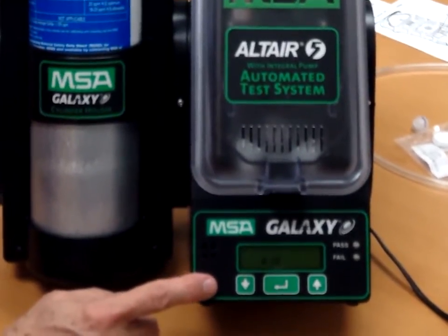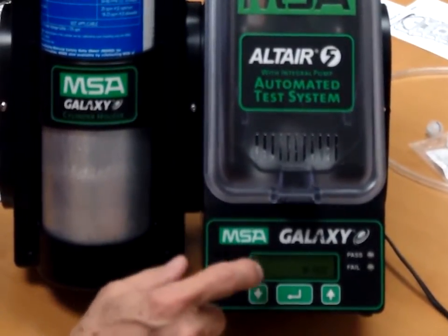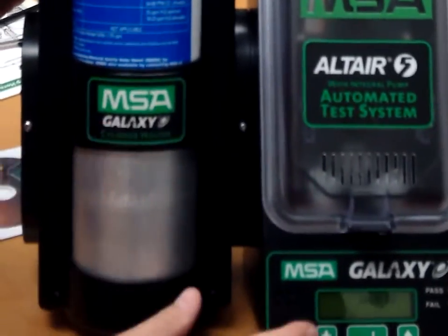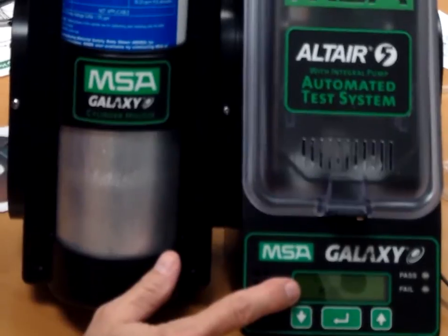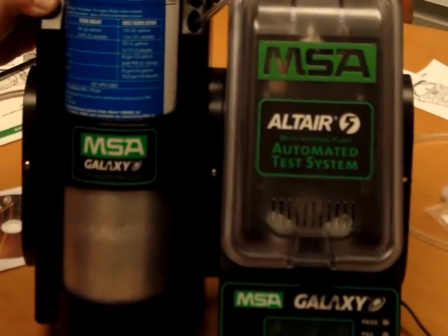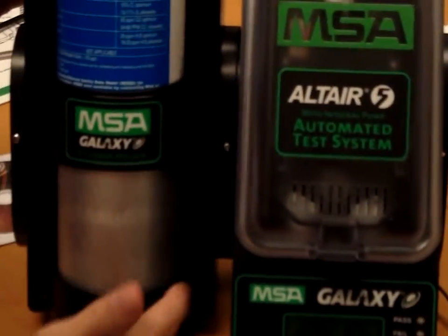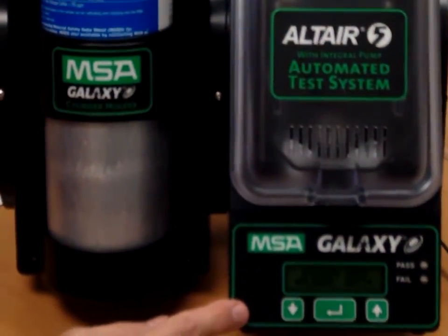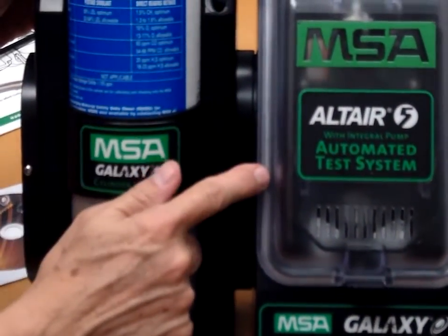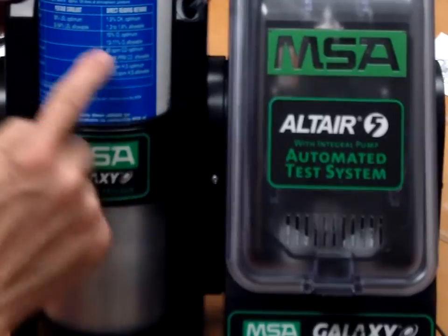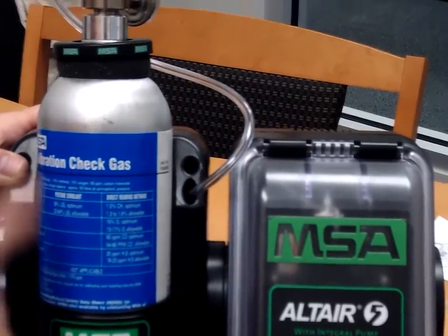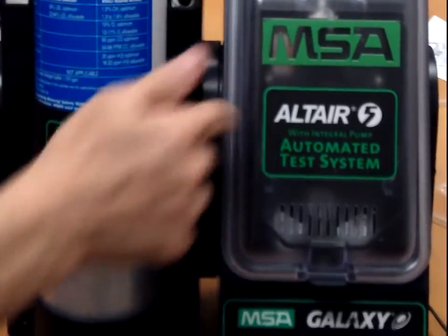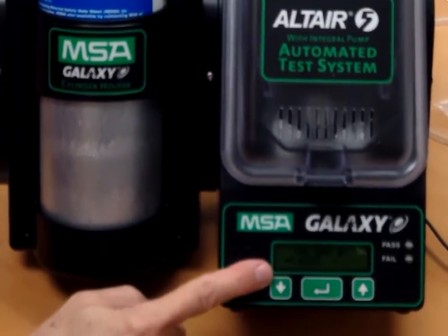When it does get through and goes through the calibration mode, what you're going to see on the screen are these numbers that are going to flash up for each one of the represented gases. Alright, we just had a successful zero, so that means that the sensors are now zeroed out, and what's going to happen at this point is that the solenoid switch is going to open up inside here and click on and allow for the gas to flow from the regulator into the tube and on into the unit. And here we go right now.